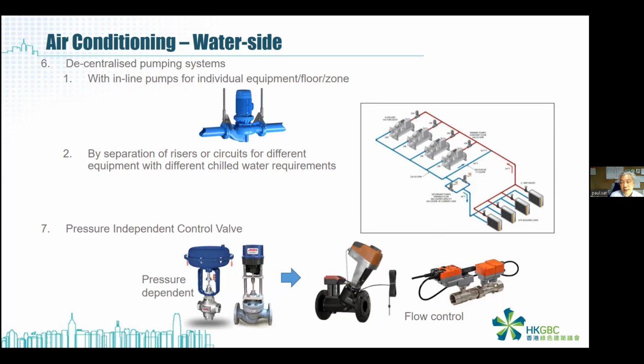in recent years, people developed some kinds of flow control valves. They call it the pressure independent control valve, in short form PICV. This kind of valve does not directly use the temperature to control the valve opening. They would use it in parallel with the control valve. The control valve can use the flow rate to control the valve opening. So the benefit of this kind of control is that the valve can be operated in a very low flow condition.